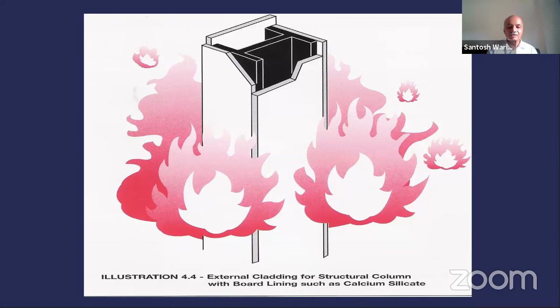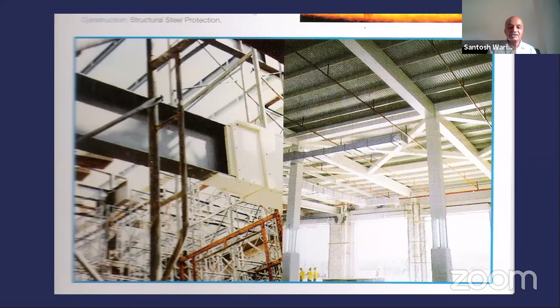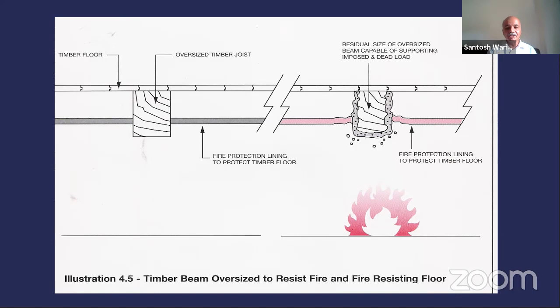Now paints are also available. You can apply the paints on this. That will give you 120 minutes or 4 hours fire rating. So these are the normal steel protections used in warehousing and major industrial buildings where the potential risks are more or high hazard activities are carried out. Again, you can have any of the old timber mats or beams or columns. You can protect them with a separate cladding by giving a layer of fire resistance material having a rating of 120 minutes.